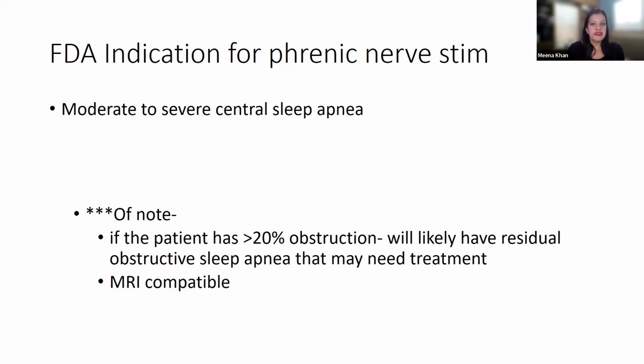So the FDA indication for phrenic stimulation is moderate to severe central sleep apnea. So it's quite broad. There are not exclusions. The patient does not have to try and fail PAP therapy. They don't have to have a minimum number of obstructive apneas. If they have moderate to severe central apnea, they can be implanted. Although you do have to have some caution. If they do have more than 20% obstruction, they likely will have residual obstructive sleep apnea. That's going to require some sort of treatment.